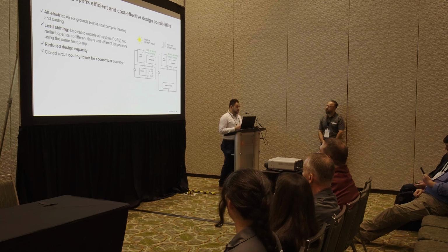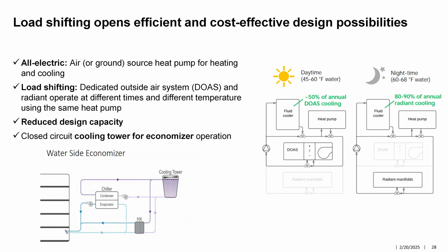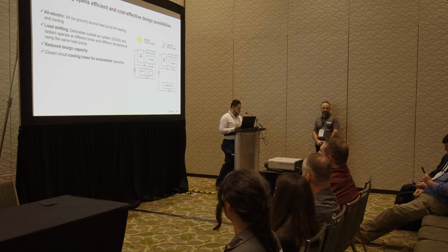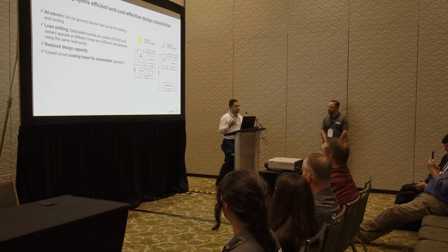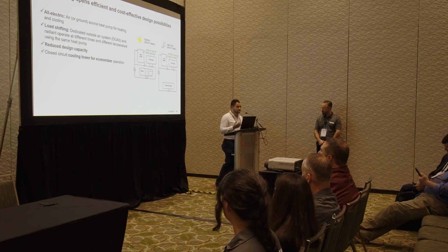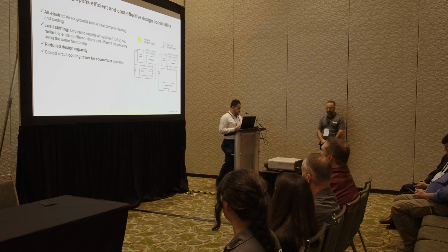The combination of high thermal mass and the large surface areas opens up the possibility to use more energy efficient HVAC equipment, such as these heat pumps. And furthermore, high thermal mass radiant systems allow us to decouple the HVAC operation from the building occupancy hours. And we can start to think about which of the hours in a 24-hour day might be best to operate the systems. So it might be a time when there's lots of solar energy on the grid, so maybe the price is inexpensive, or you start to think about when the grid emissions are also very low, so you can target those areas of operation.